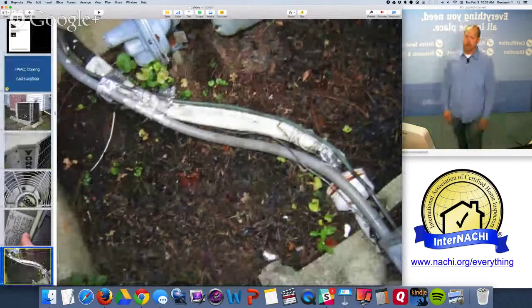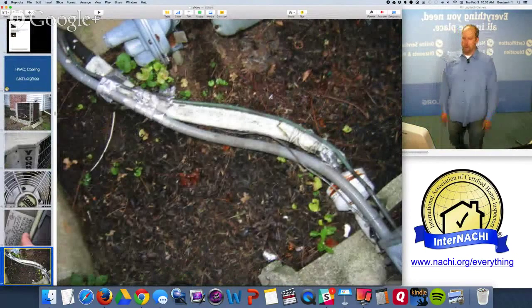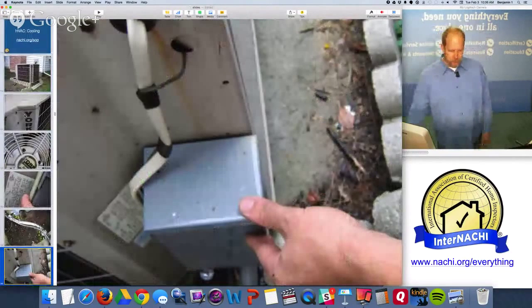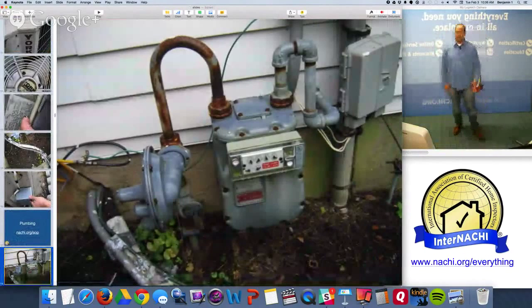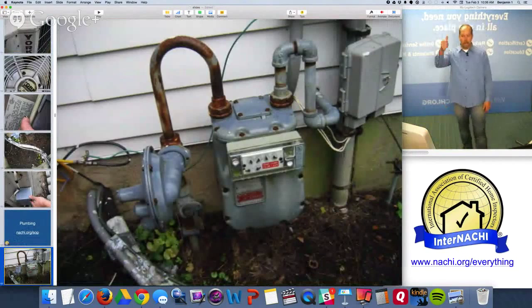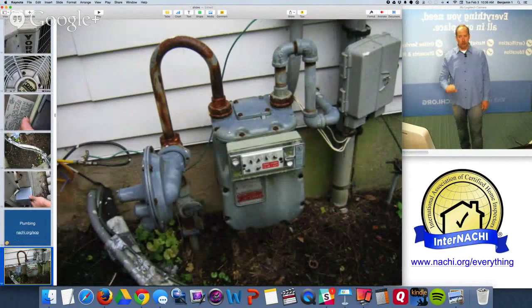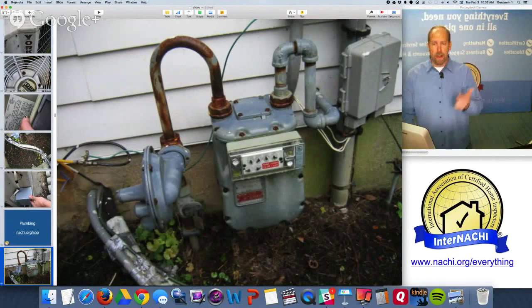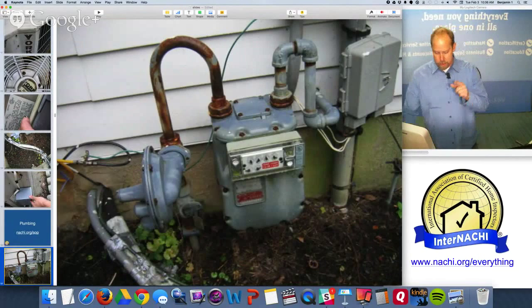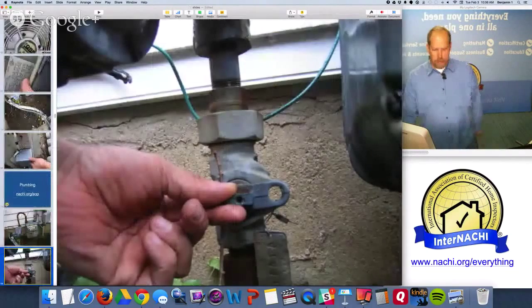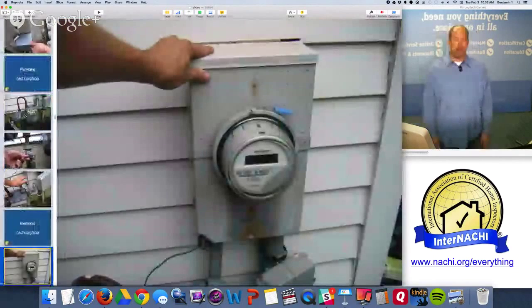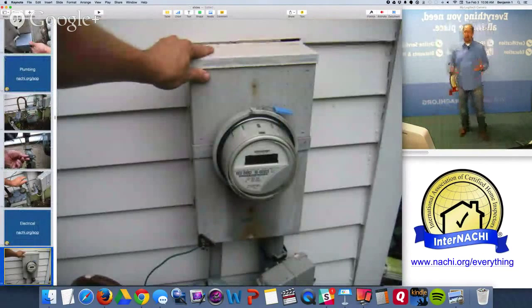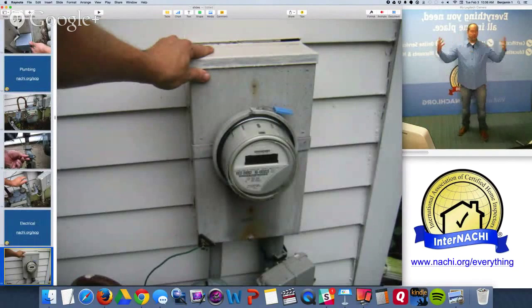The HVAC cooling compressor/condenser unit is on the outside. The suction and refrigerant lines are not well insulated; the dryer looks a little rusty and old. There's a shutoff/disconnect switch inside the unit. The plumbing is also outside - natural gas is publicly supplied to the home. The line comes up from the street through a shutoff valve (which is in the off position), a pressure regulator, then the gas meter, then back into the home. Anything that penetrates the exterior wall coverings is a potential pathway for water, moisture intrusion, and vermin. The line going in is not sealed.